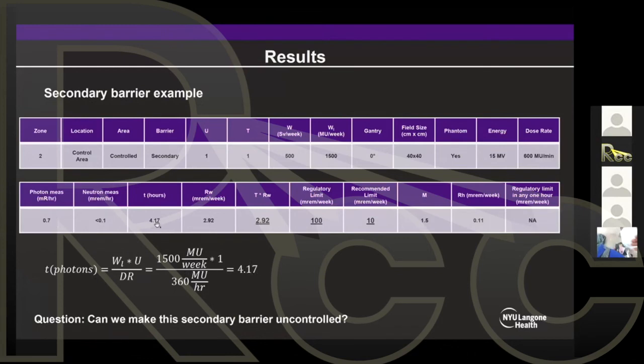So now you're going to multiply these two numbers. You're going to get your RW, and you're going to multiply by your occupancy factor. So you get to 2.92. And again, you compare: this is my regulatory limit, this is my recommended limit. So all good, I'm actually well below this limit, right? And again, I'm going to get the any given hour number. So I'm going to multiply 1.5 and divide it by 40, and that's 0.11. Because this is a controlled area, this limit doesn't apply. This will only apply for an uncontrolled area. And we know it's 2 millirem in any 1 hour.